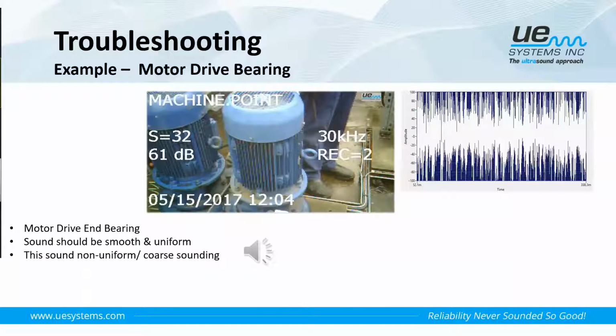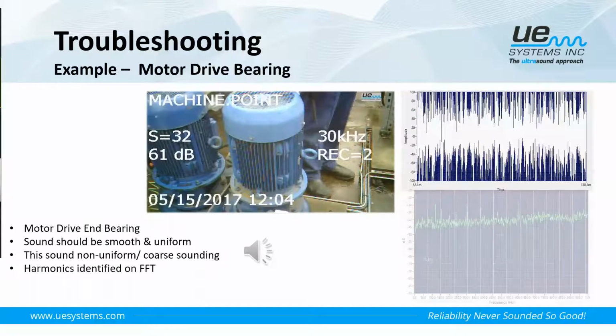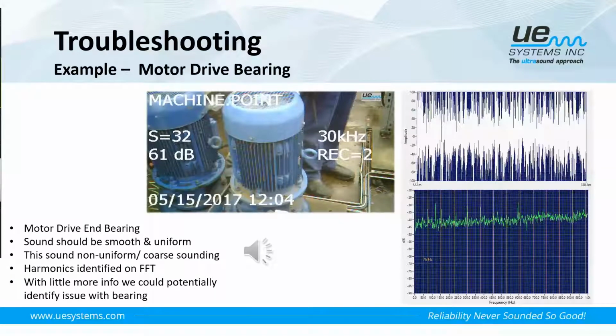So as we can hear from that sound, it was non-uniform and coarse in nature. As we can see from the ability to take a sound recording, we can see from the time waveform that the sound does not look smooth and uniform. We can see very large amplitudes and impacts in the time series. In the FFT side of things, we can also see harmonics, and we can see harmonics in this recording at approximately 75 hertz. Now, from a troubleshooting perspective, we can already gauge that there's something not right with this bearing. If we had a little bit more information, like the rotational speed, the type of bearing and the number of rolling elements in there, we could make a further diagnosis as to what is actually occurring. But for ultrasound's purposes, we've identified here that this motor requires further investigation.